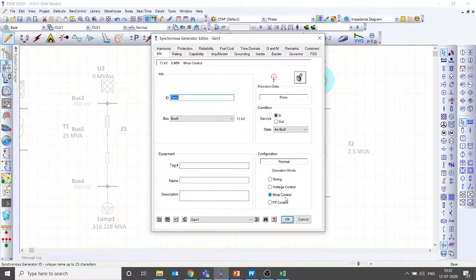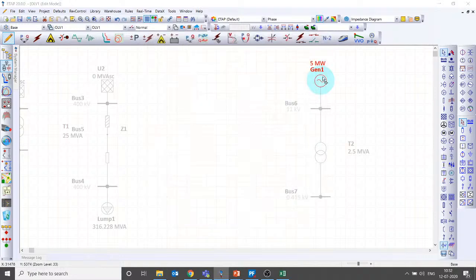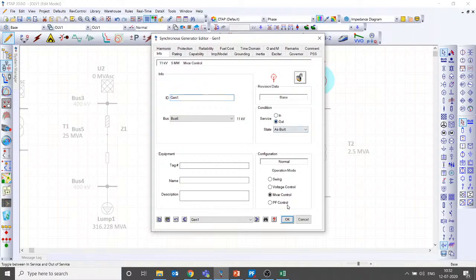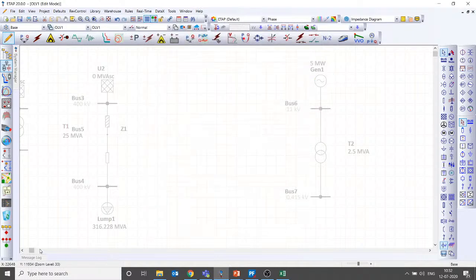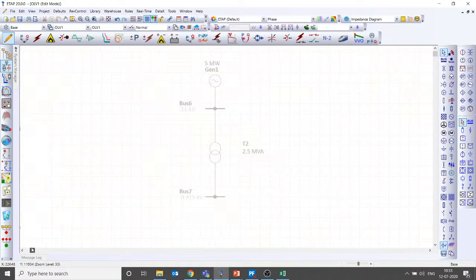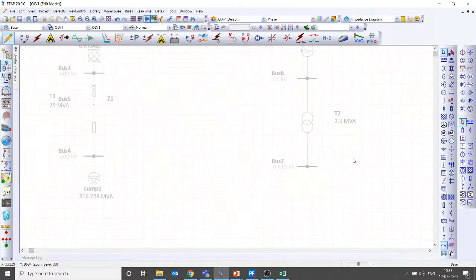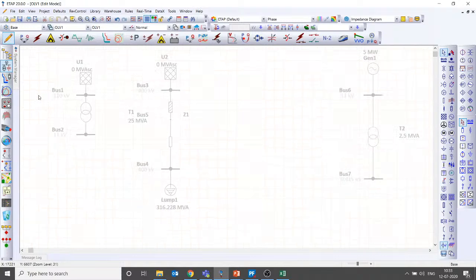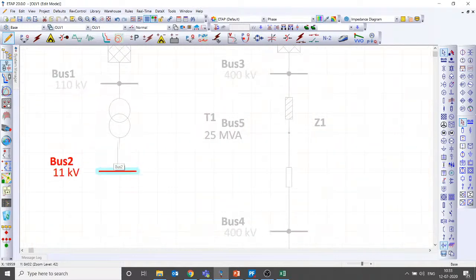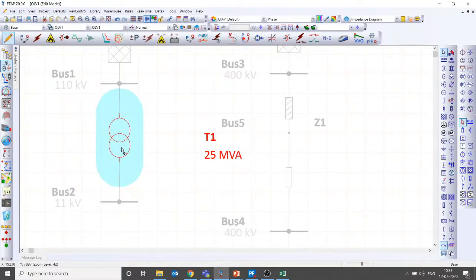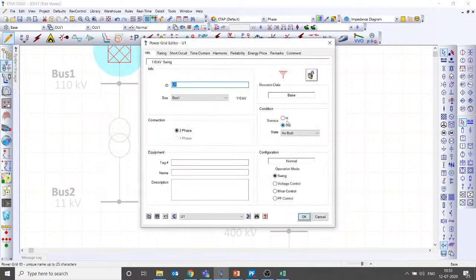But if I put the same generator in power factor control mode, then when the real power changes, the reactive power also changes. So let's have a small example to prove that. That will be interesting. Let me go back to my first system. Let's take the same example, 110 kV and 11 kV. Assume that at this 11 kV we have a generator, and let's enable the grid.